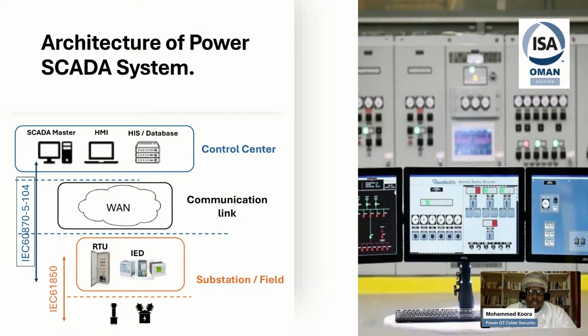We also find a device called IED, intelligent electronic device. It is a numerical relay, and it acts like a brain for the protection team. Whenever anything happens, it reacts. They have a set point, and from that set point some action happens, like opening a breaker or other things.